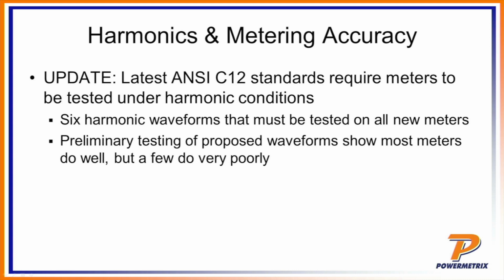Something the ANSI committee did do recently is decide to add 6 harmonic waveforms to the C12.20 standard, which is basically the standard by which all modern solid-state meters are built. Meter manufacturers have to do something called type testing, meaning they have to go through all of these different tests before a meter is released out into the real world.